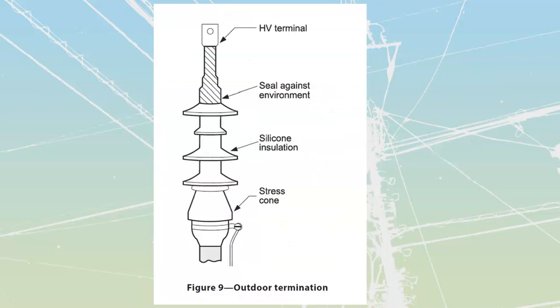Last of all, we're going to take a quick look over here at a class 1, or outdoor, termination. This outdoor one is going to provide stress relief, anti-tracking, and protection against the weather. Same deal, this one is going to have a stress cone component.